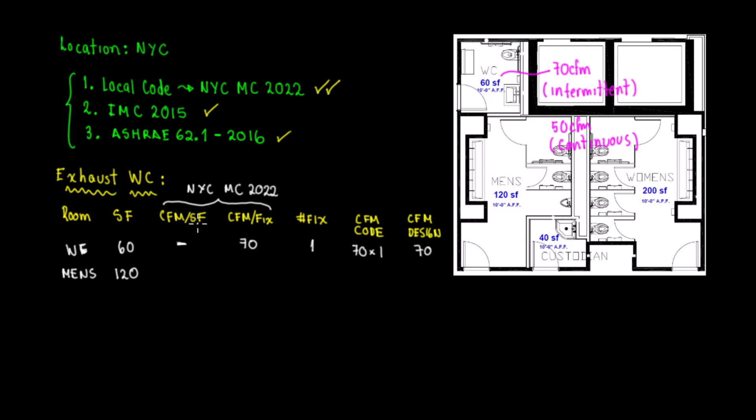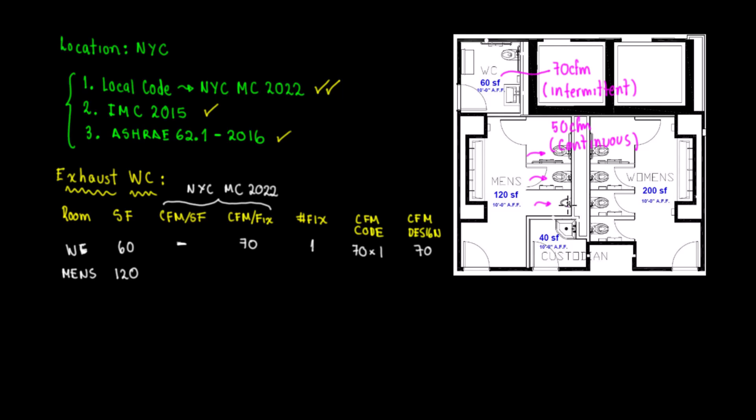What kind of fixtures do we have? We have toilet number one, toilet number two, and one urinal. How much CFM per fixture do I need in order to exhaust and comply with code? The CFM is 70 CFM per fixture.